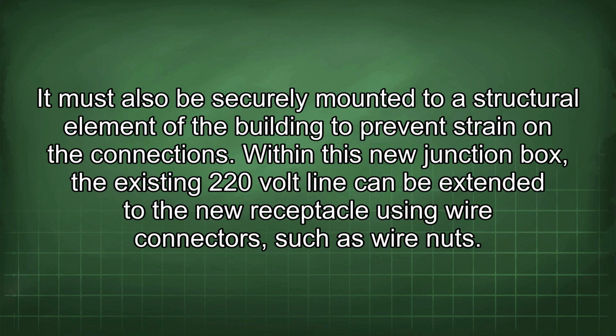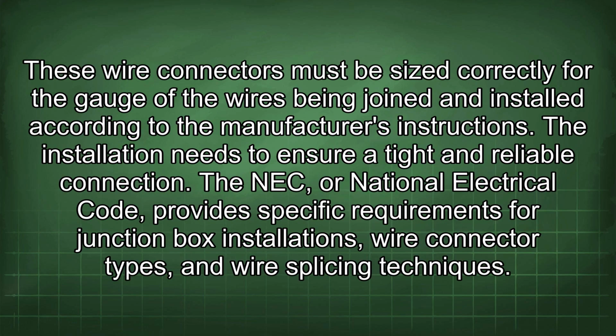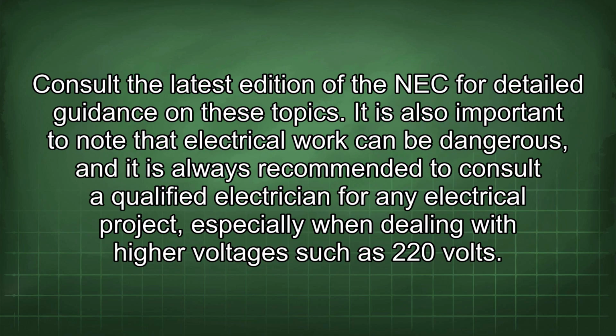Within this new junction box, the existing 220-volt line can be extended to the new receptacle using wire connectors, such as wire nuts. These wire connectors must be sized correctly for the gauge of the wires being joined and installed according to the manufacturer's instructions. The installation needs to ensure a tight and reliable connection. The NEC, or National Electrical Code, provides specific requirements for junction box installations, wire connector types, and wire splicing techniques. Consult the latest edition of the NEC for detailed guidance on these topics.